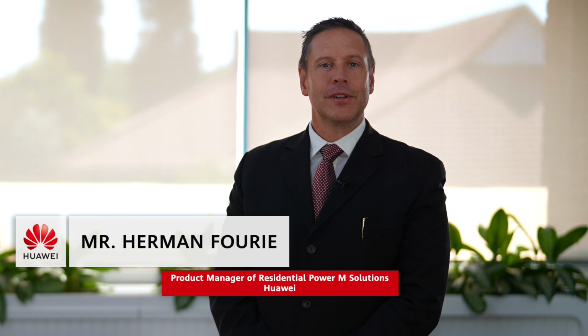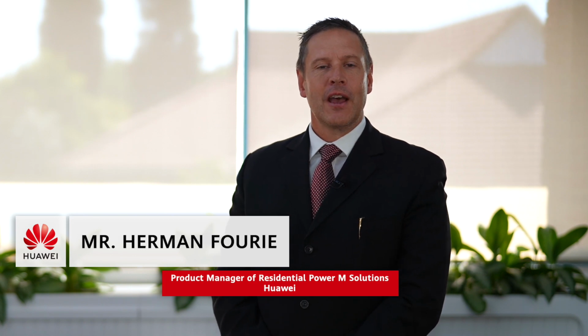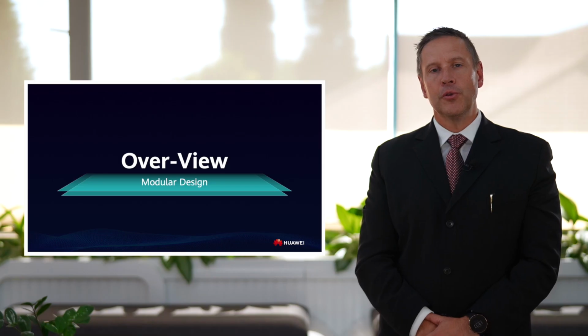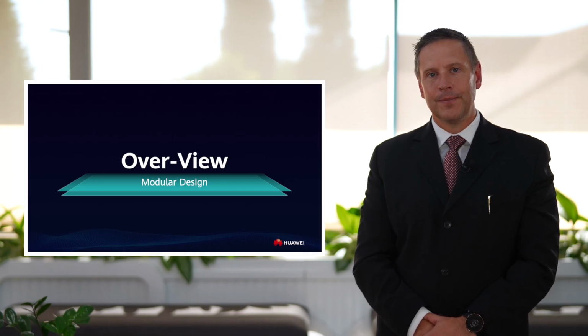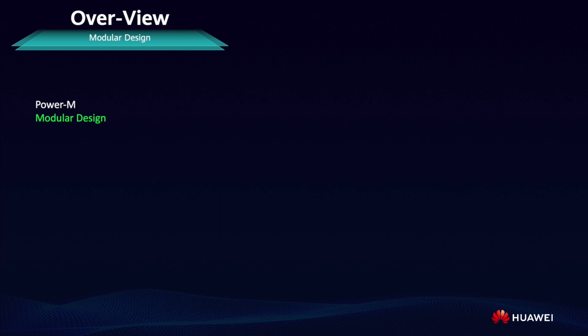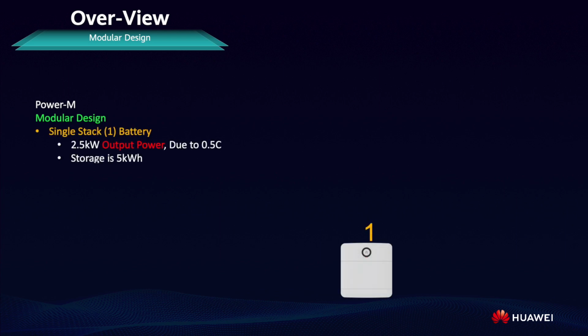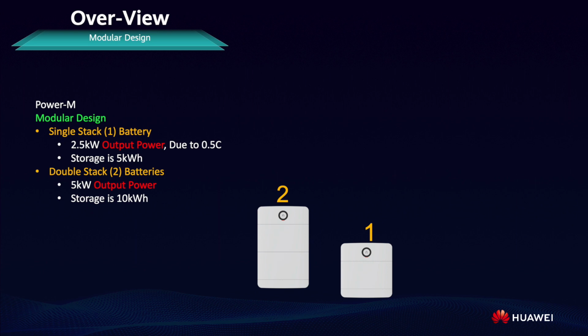Today I will take you through the technical advantages of the product, where I'm going to start today on the modular approach. Overview, modular design. The Power M modular design in the single stack battery is capable of providing 2.5 kilowatt of output power due to the 0.5C rating. The storage is 5 kilowatt hour. In the double stack 2 battery configuration, the unit can provide 5 kilowatt of output power with a storage of up to 10 kilowatt hour.